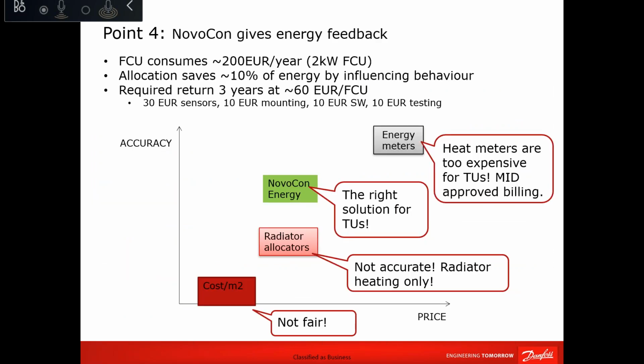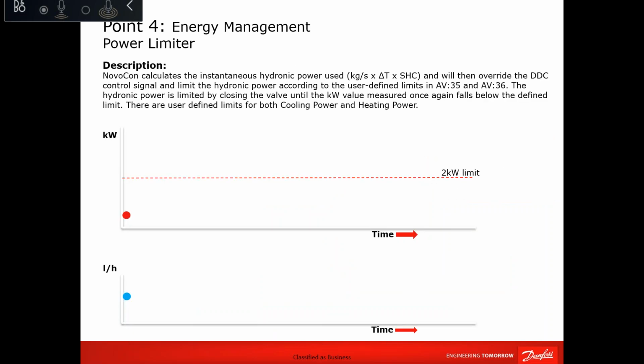If we take the feedback on the energy from the actuator, since we said that it has a temperature sensor, it can indicate the flow, then you can track the energy, you can find out what the consumption is, and you can tune that consumption to reduce it. So in this example, changing some of the behavior can give you 10% of energy saving without doing anything. It's only changing some variable from the BMS.